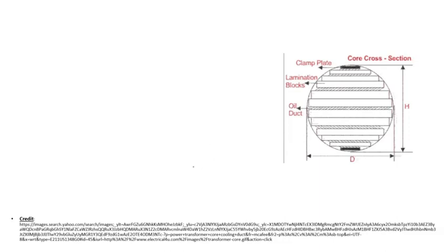Again, I took this picture from the internet, and I want to give them credit. When you look at the core, this is core form. Shell form is kind of similar but can be different. It's kind of a round section, so you have steps, lamination blocks, what they call steps. Because the core is huge, they might insert some of these cooling ducts, which might be made of porcelain. Basically, you want to create a gap such that oil can flow easily between those sections. Some people might use press board with some kind of sticks to create paths for oil to flow. There are different ways people do it, but it's intentional, basically creating a gap.